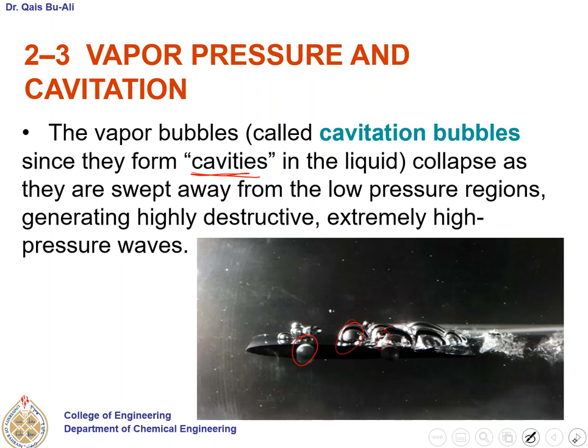And what is the effect of those high pressure waves? As you can see, this is an impeller. Okay, so erosion on the blades of the mixed flow pump, as you can see on the impeller. So once they collapse, they will start to cause erosion on the blades. So this phenomenon is called cavitation, and it is an important consideration in the design of hydraulic turbines and pumps.